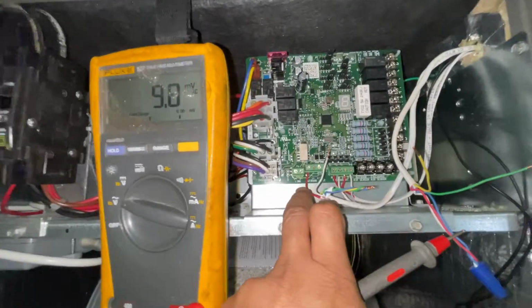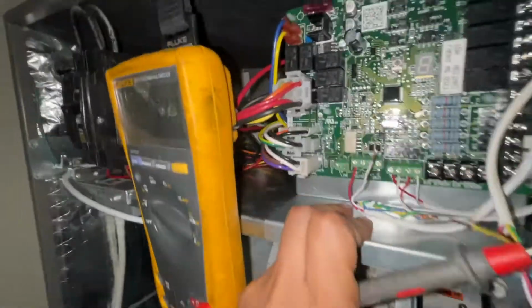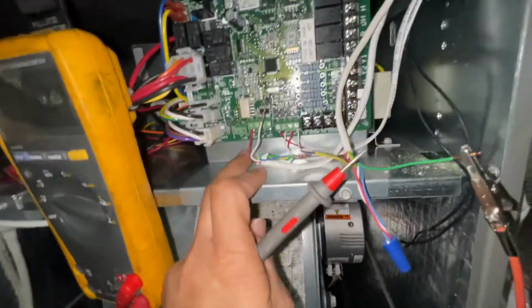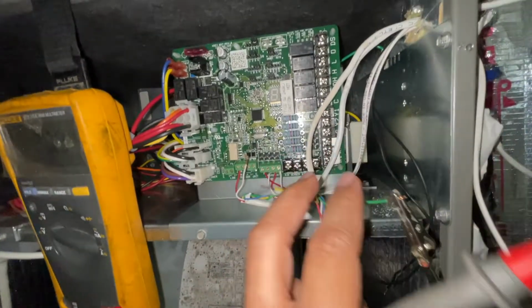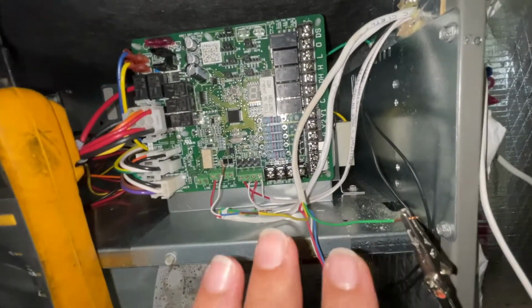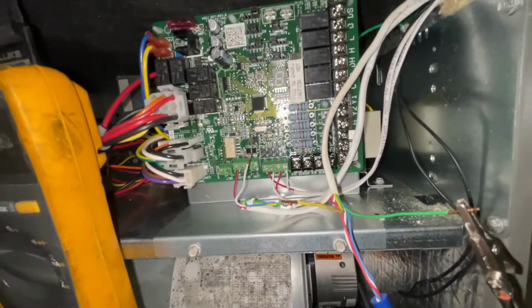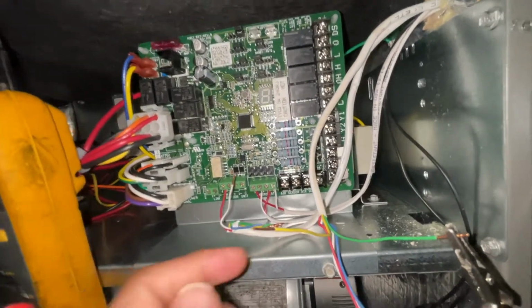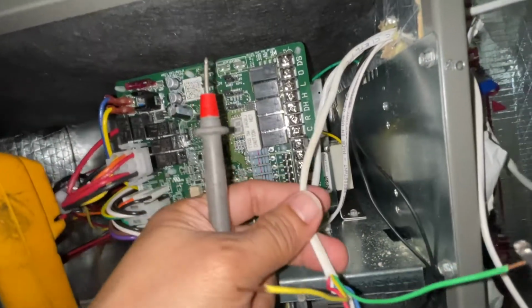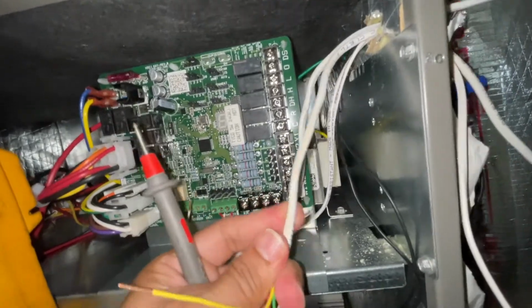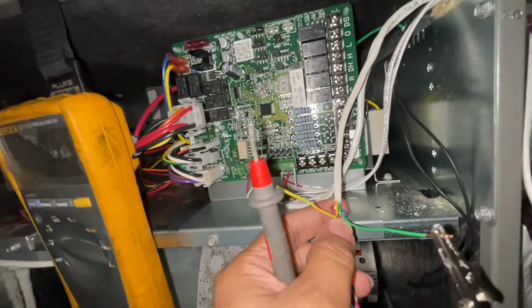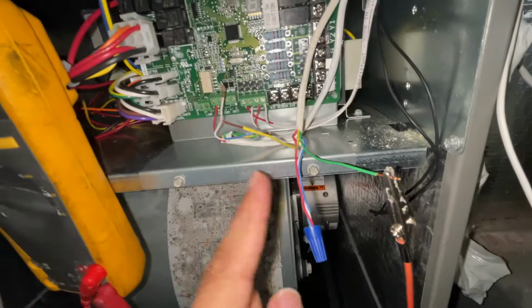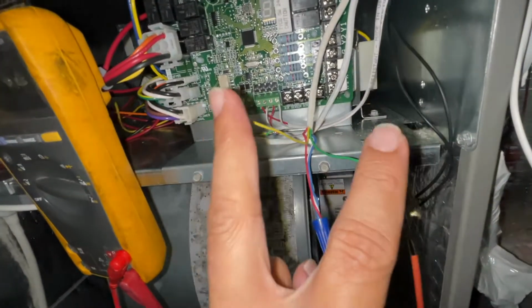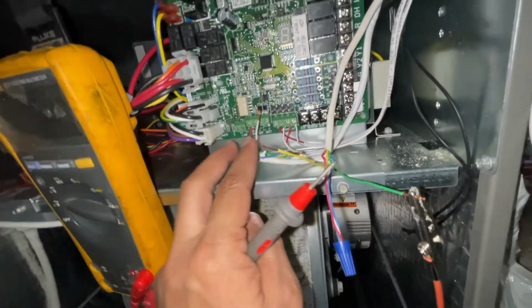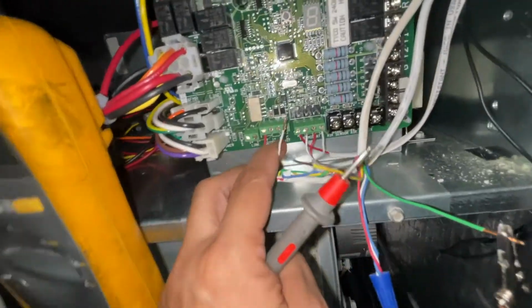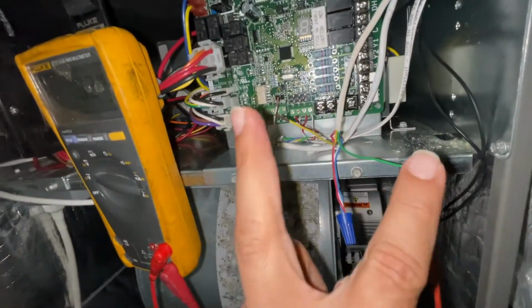Make sure your red wire is plugged in when you're doing this test. In my case, it was plugged in. I'm going to do the same test on this wire. This is a spare wire that is going out to the exact same outdoor unit. My builder for this house ran two wires. I want to see how much transient I'm getting on this wire, because if this wire is not getting a lot of transient, then this might be a good source for me to use for communication. I can leave the red and the common on this one and use my communication for this one.